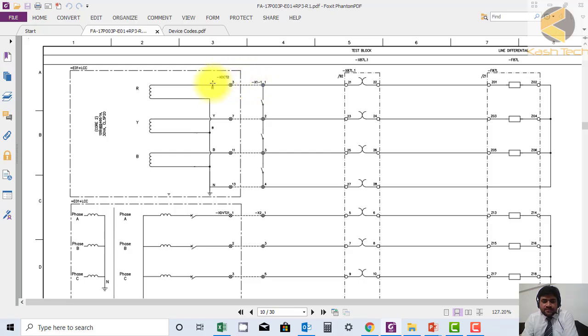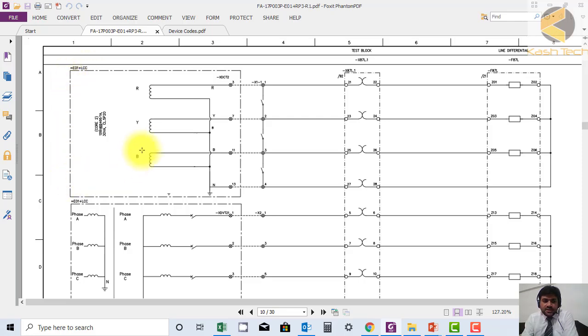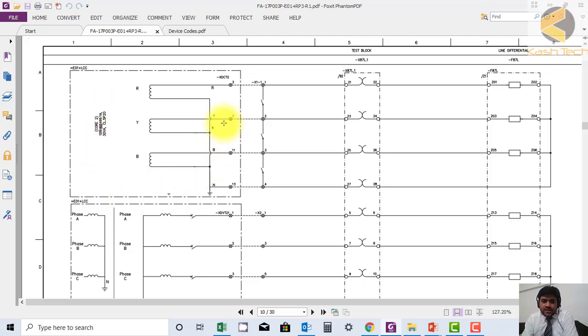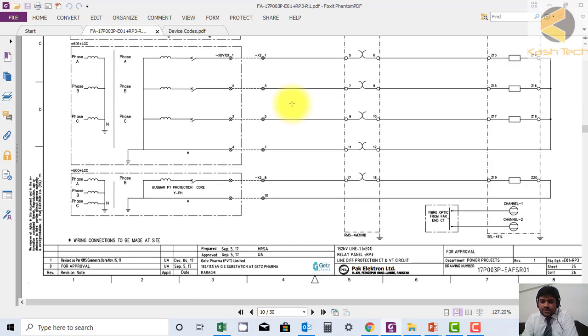Here you can see again the dash and dot line, this is coming from LCC panel of bay A01, this is external wiring. X1-1 is internal and it is connected to X DC T23. This is how the external references are mentioned. External panel is drawn with the reference line dash dot dash and it is connected. This is the way of internal and external connections.